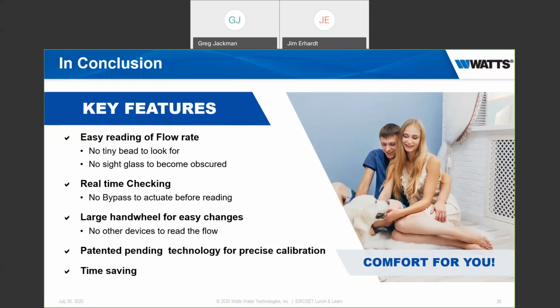Patent pending technology for precise calibration, again, plus or minus 10% is the worst case scenario. It's actually better than that throughout most of its range. And as you can probably see by now, if you're used to working with standard circuit setters, it's a time-saving process. It's going to save you a lot of time on a job and get you in and out a lot more quickly than using a standard circuit setter.